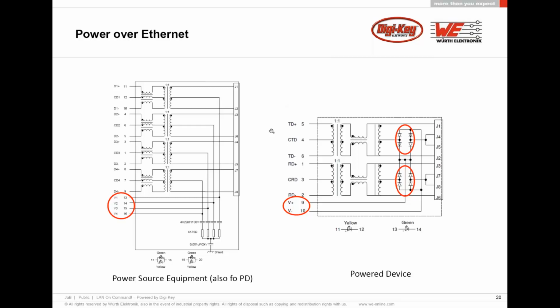Here we can also see there are some slight differences between the schematics. If I'm having an RJ45 or a transformer, this applies rather for an RJ45 for a PD or for a power sourcing equipment. As we can see here, we have 4 different pins for the PoE. So over J1, 2, 3, 6, 4, 5, 7, 8, I'm putting in my DC current, and somehow it's coming out here, then going up to pins 13, 14, 15, and 16. As you can see, we have no diode bridge here, so this is a clear example of an RJ45 for power sourcing equipment. If you use it for a PD, you need to make sure you have the diode bridge here. In this case, because we have the diode bridge, it is for a power device.